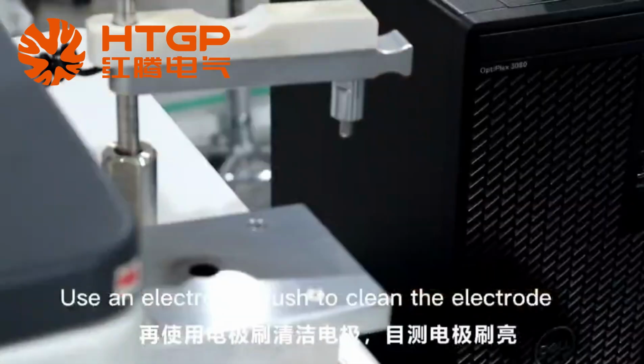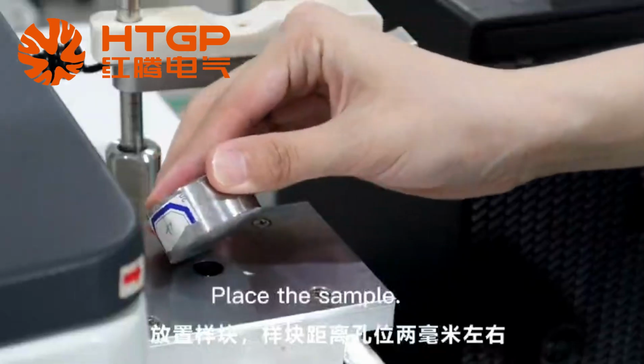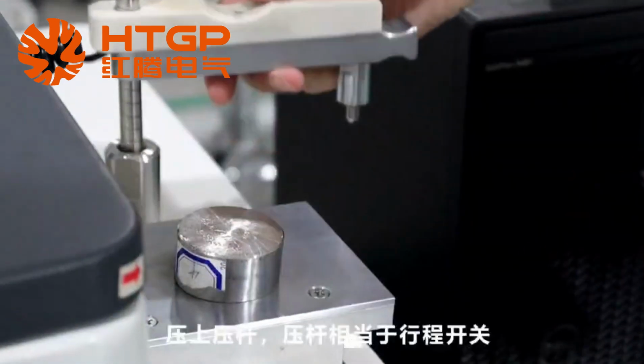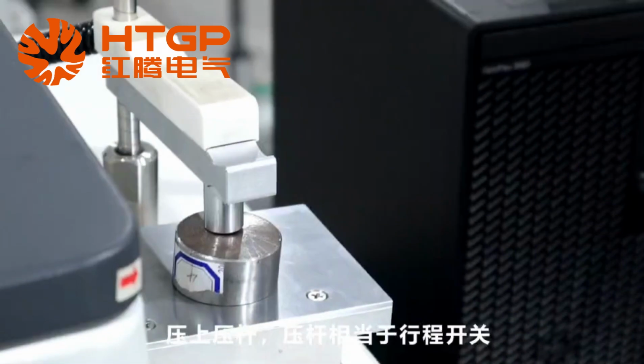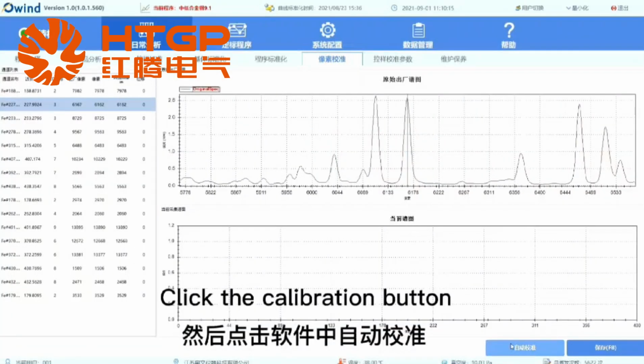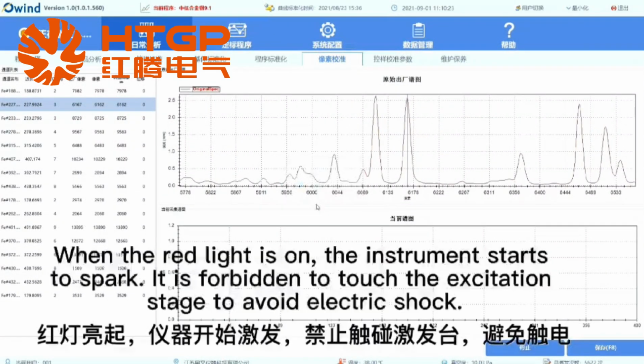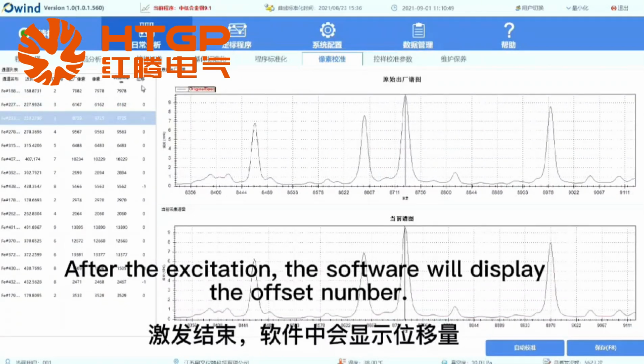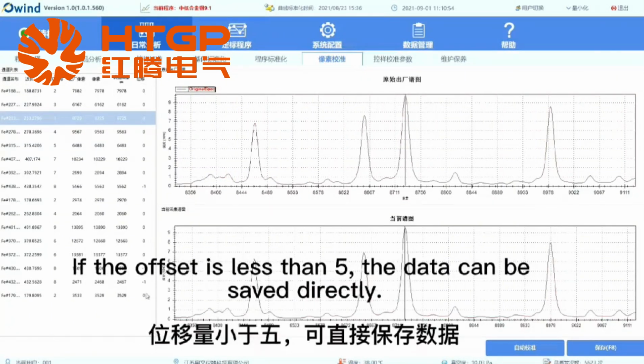Use an electrode brush to clean the electrode. Place the sample. Click the calibration button. When the red light is on, the instrument starts to spark. It is forbidden to touch the excitation stage to avoid electric shock. After the excitation, the software will display the offset number. If the offset is less than 5, the data can be saved directly.